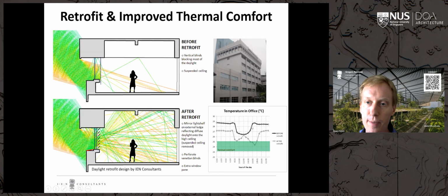We did some temperature measurements before and after. The black curve is before - it's a bit difficult to read, but you can see the aircon was switched on at 8 in the morning, and it only dropped to about 26.5 degrees, so it was actually not a very cool office, a bit uncomfortable. To save energy, they switched off the aircon as well as the lifts at 3pm. I used to work in this office, so it was really hot to sit there, and you can see the temperature went up - you're basically sitting in a non-air conditioned office towards the end of the day.